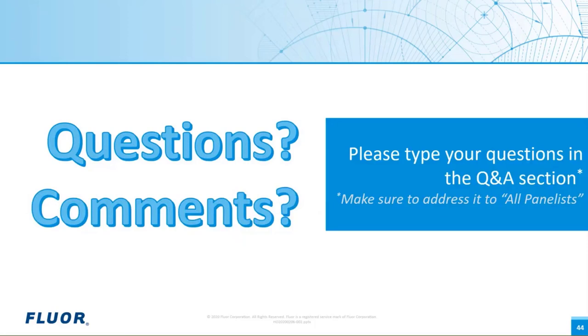So there's another one here. Maybe Eddie, you can take this one. How does this apply for ongoing projects that are already in construction? I've seen that. Several people asked that in the question and answer session here, and it is very important to realize where that line in the sand is, where you have to comply with this new rule. If something was designed prior to the 2020 change, then in my opinion, it depends on the authority having jurisdiction, but most authorities having jurisdiction that I've worked with across the United States and internationally won't make you apply the new rules retroactively to an existing design, because that would be a nightmare if you had to start increasing equipment sizes and buildings that have already been built.